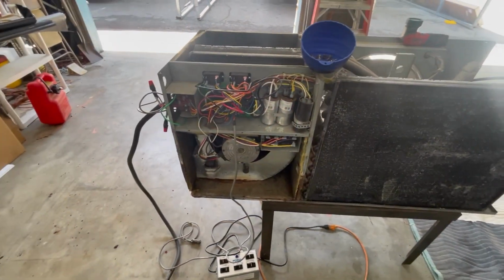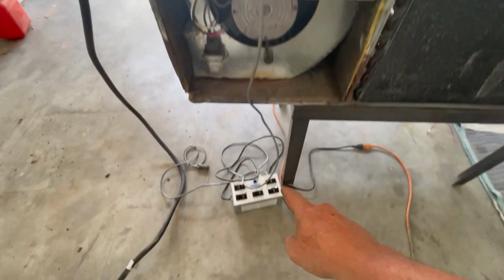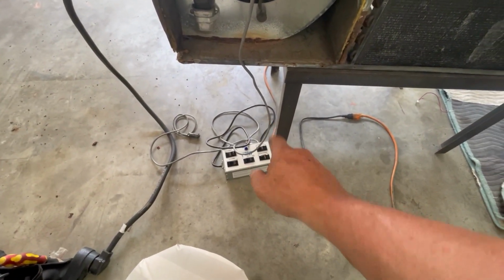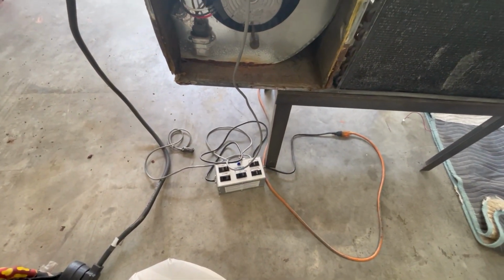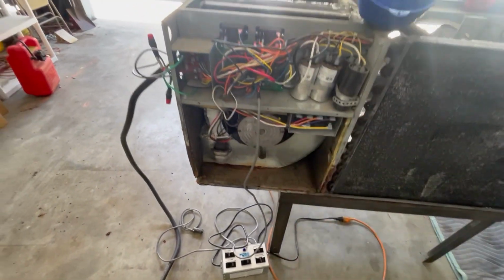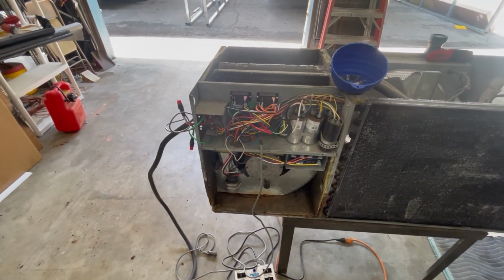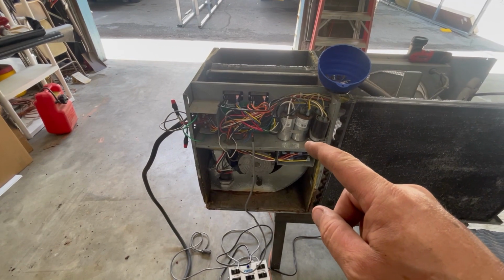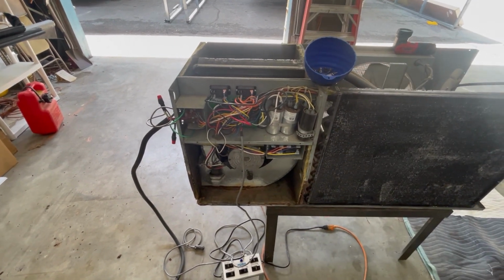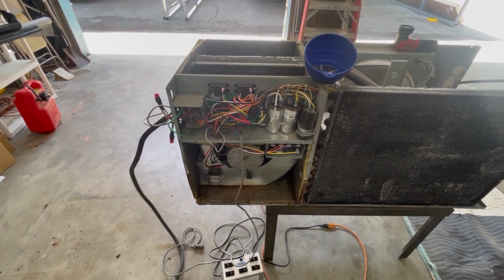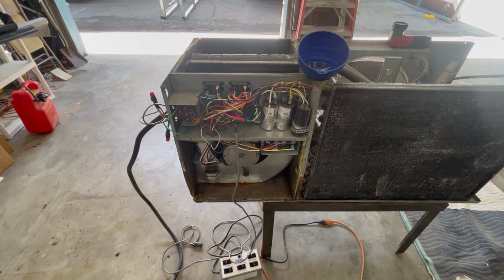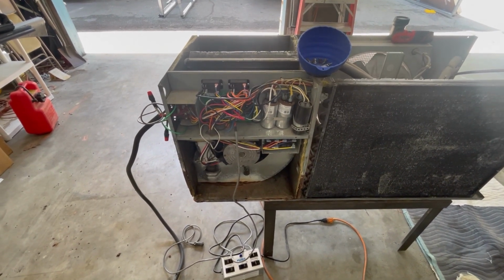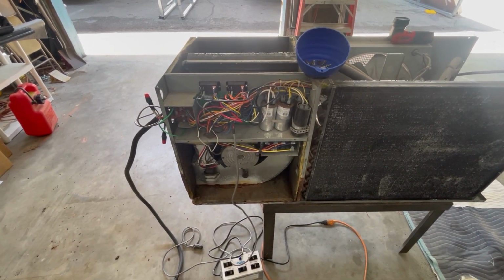Lewis and I found out it was not the control board - actually the transformer in our test box wasn't putting out enough voltage to operate, that's what was going on. So we ran the unit and we do have a bad compressor 1. We're going to get the new compressor pulled out, get it brazed in, then get it charged and retest.